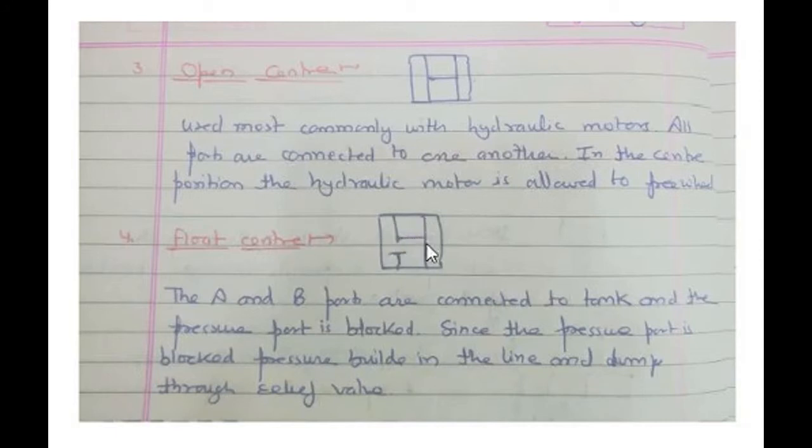Number four is float center, in which port A, B, and T are connected to each other and the pressure port is blocked. Since the pressure port is blocked, the pressure builds in the line and it has to be dumped through the relief valve.